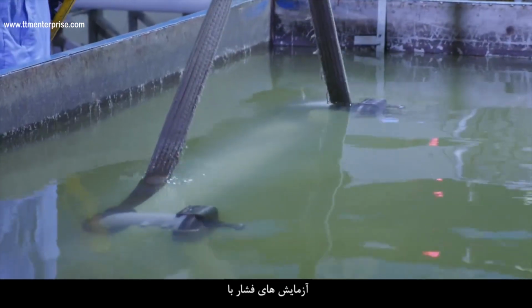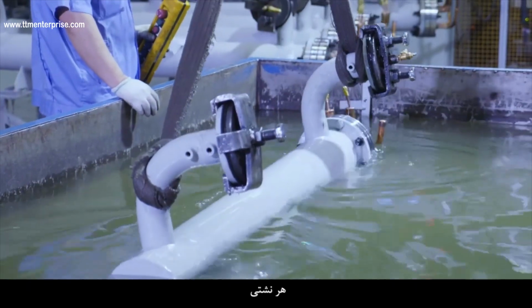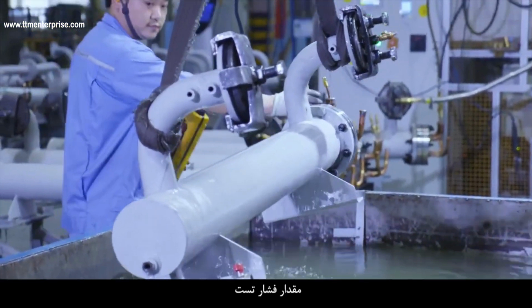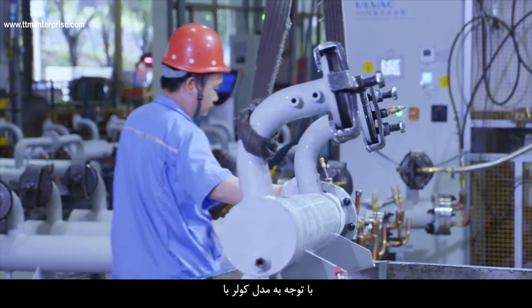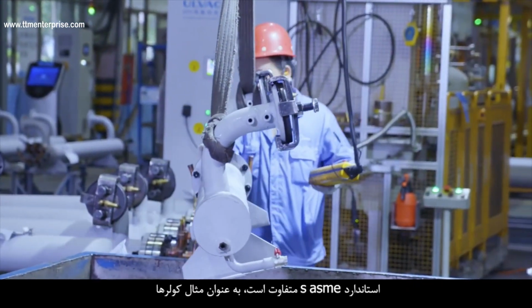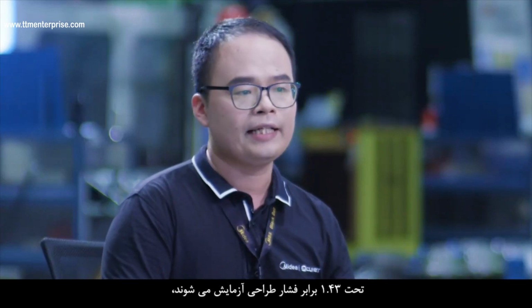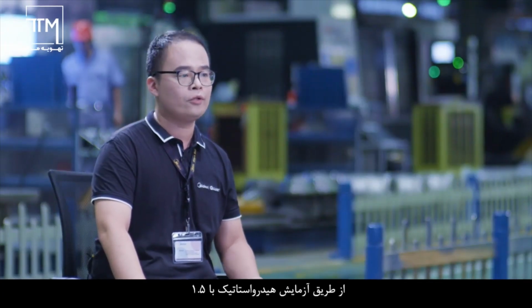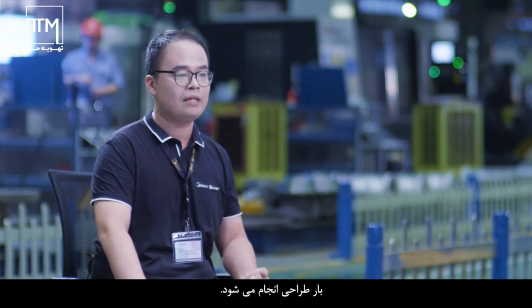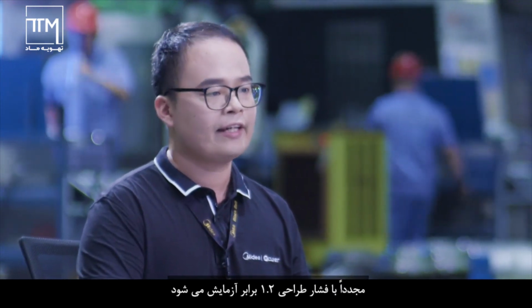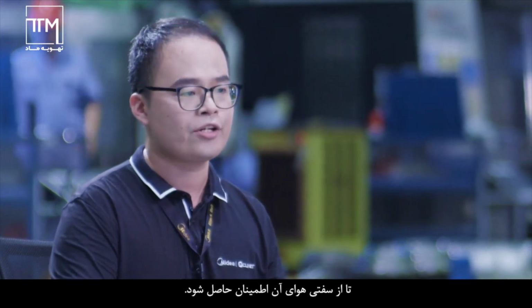After the coolers are manufactured, a pressure test will be conducted at a higher pressure to ensure there is no leakage. The value of testing pressure varies with the cooler model. Take the ASME standard for example. The coolers will be tested under 1.43 times of the design pressure. As for the compressor, the pressure bearing parts will go through a hydrostatic test with 1.5 times of design pressure. After the assembly, the whole compressor will be tested again with 1.2 times design pressure to ensure its air tightness.